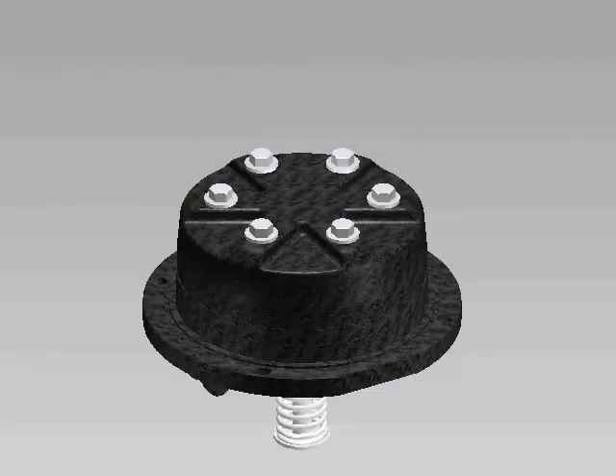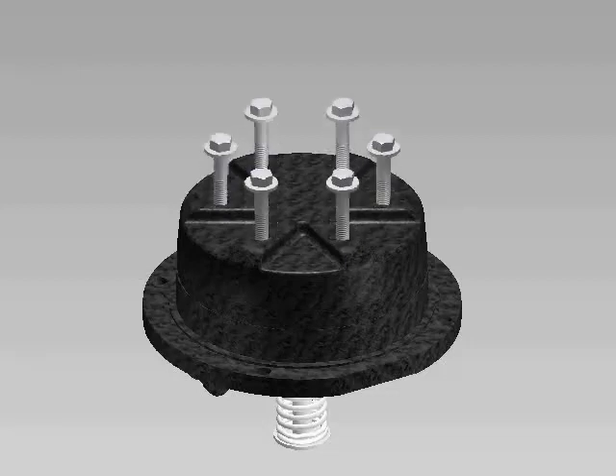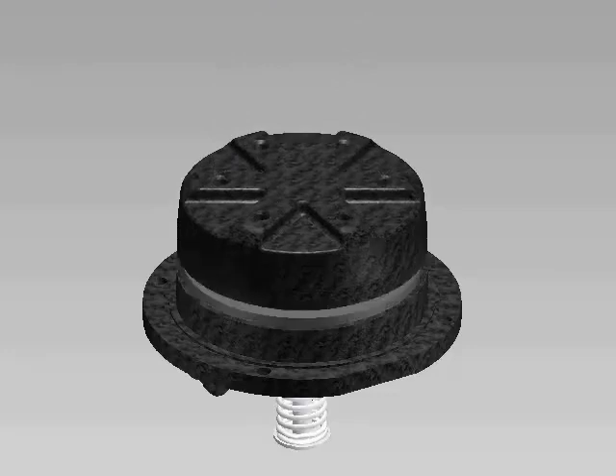Always service the checks one at a time to avoid mixing parts. Both checks can be repaired following the same procedure. You will want to remove the bolts from the seal retainer on the check, then remove the retainer.